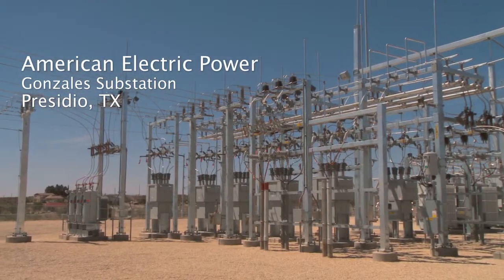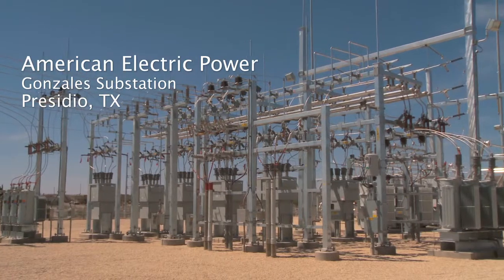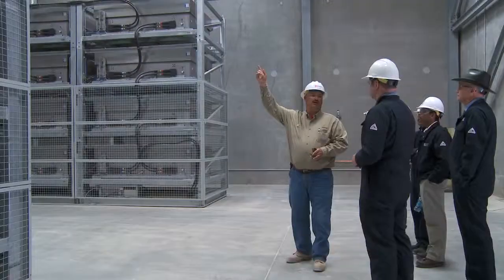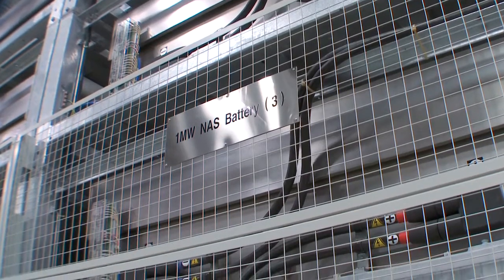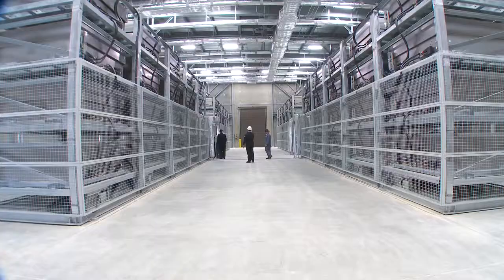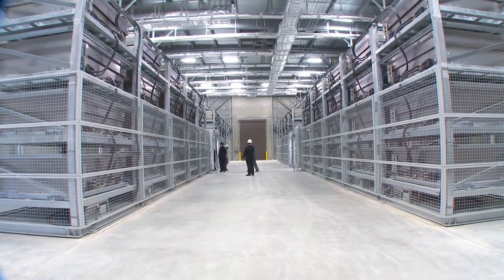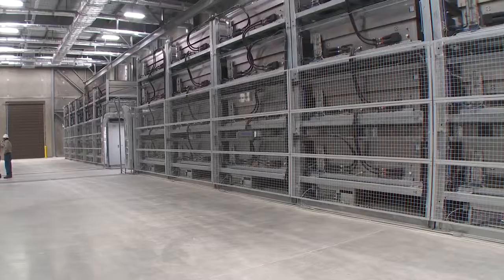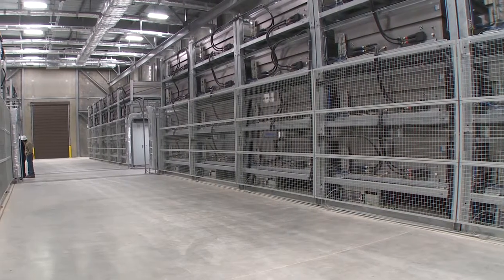For the AEP system, SCL is providing a substation automation controller to control shunt capacitor reactor banks to keep MVAR at an operator set point, battery management that includes periodic charge and discharge of the battery, and load shedding to protect the battery from too much load. It also includes auto transfer and load splitting functions performed automatically and manually from operator-initiated transfers from CFE and AEP.